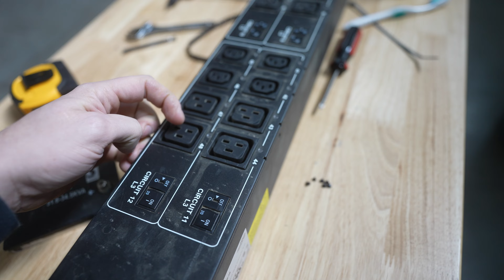When we load a miner, we'll just have one plug going to the miner, and that'll give all the power it needs from that one plug, because only one of the legs will carry the electricity. So let's say this one here is 240, this one will just be blank like a neutral, and this one will be ground. So it's 240, neutral, ground, 240, neutral, ground, that's how it's going to be loaded, instead of 240 and 240 like A-B and then ground or neutral ground. This is just going to be one, loaded that way, and each one of these will give us all the power we need. Again, we have 35,000 watts.